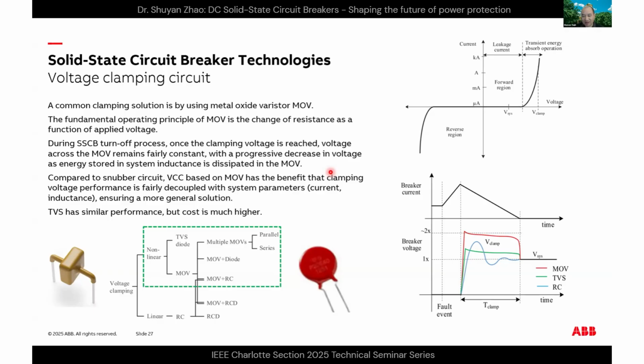You mentioned one advantage of a solid state circuit breaker is no noise. So if a fault happens and there's no noise, how does the breaker notify people there's a fault? That's a good question. Usually we don't use noise to indicate a fault in the system, because that would be very surprising or really risky - we cannot rely on that.